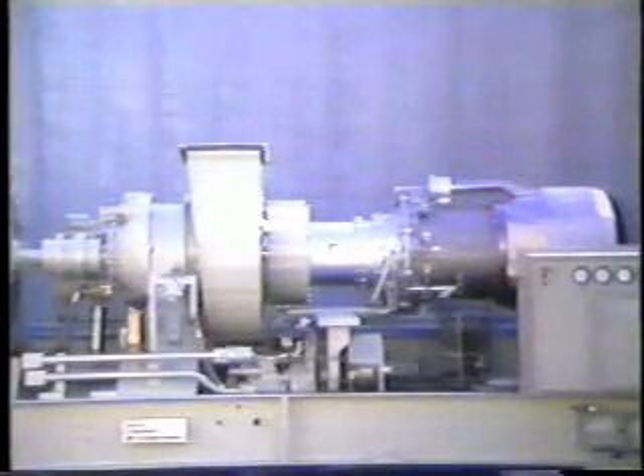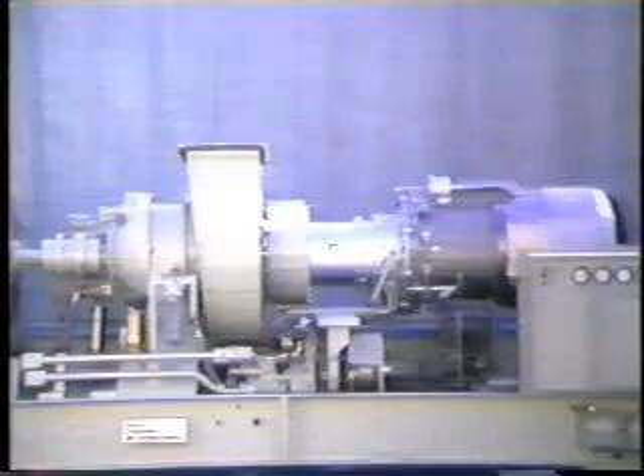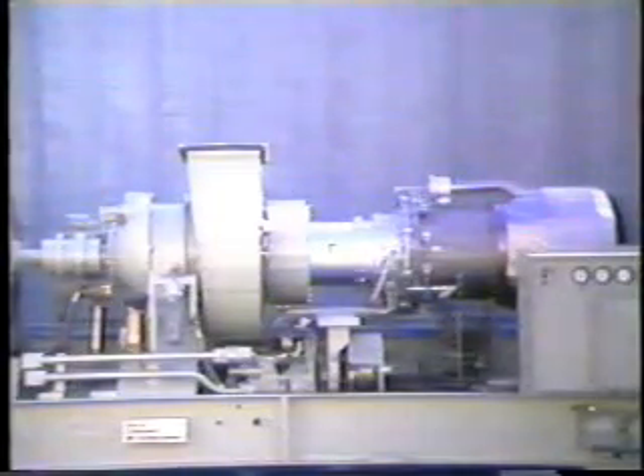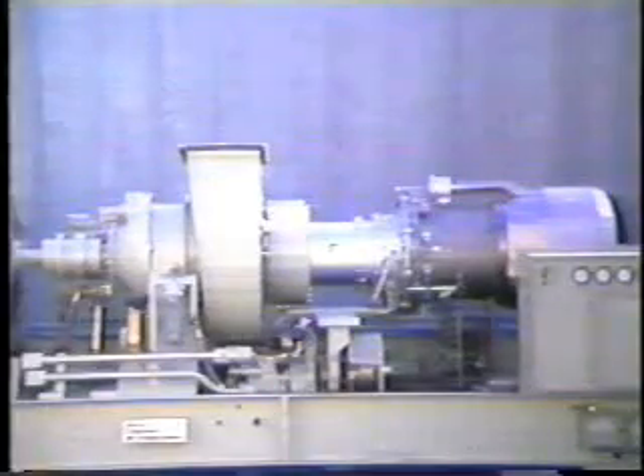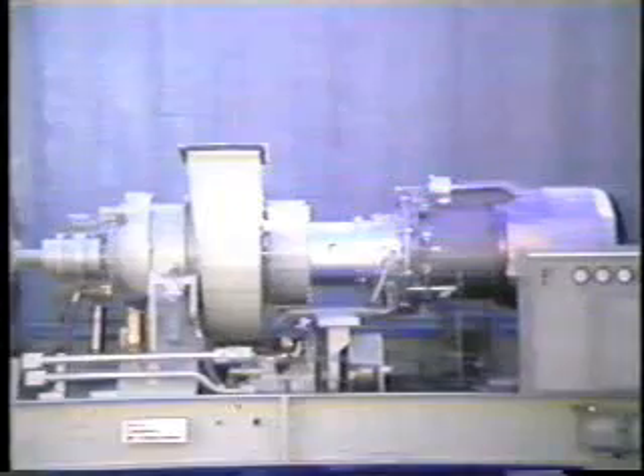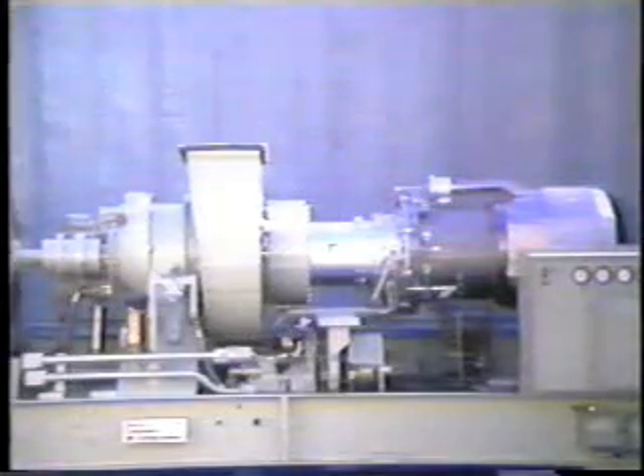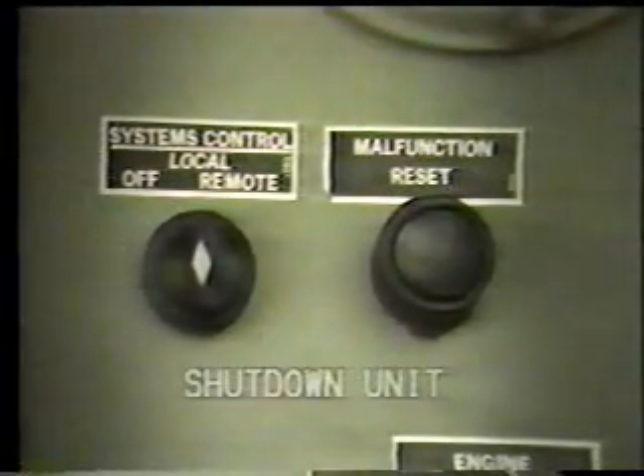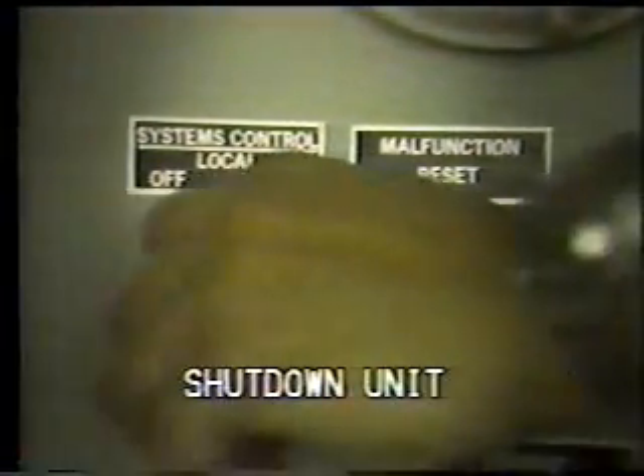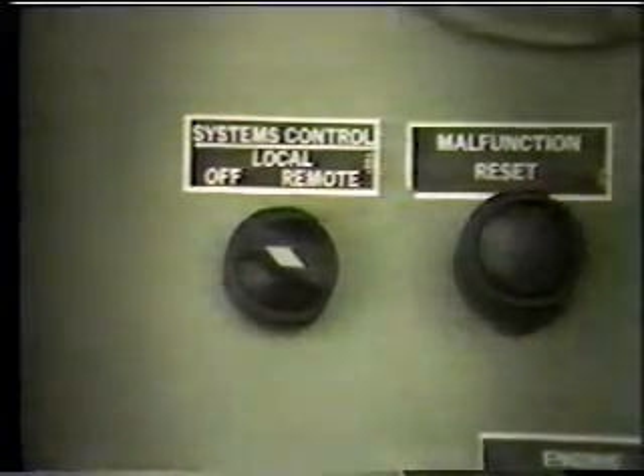During this inspection, you'll check gas producer seal and combustor drains for oil passage while the post-lube pump is operating and the lube oil is hot. Inspection of the gas producer and combustor drain is performed as a part of the intermediate maintenance section. Check your operation and maintenance instructions for warnings and safety precautions prior to performing maintenance. Shut down the units. Turn the master switch off and tag it.